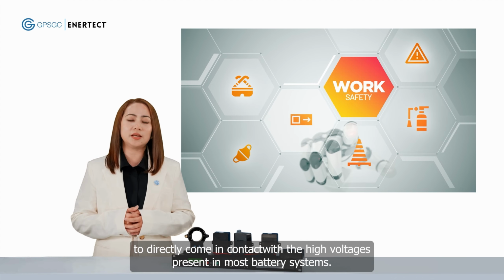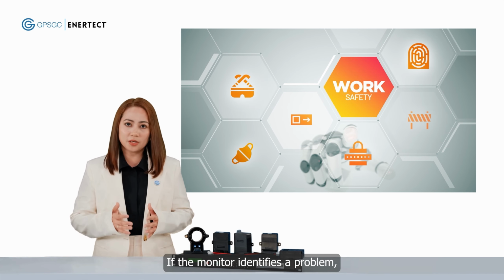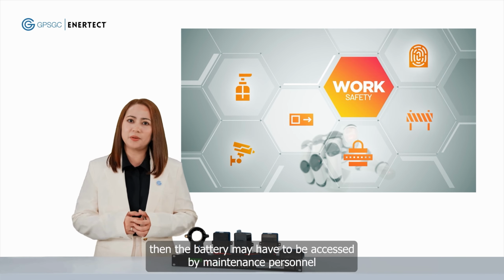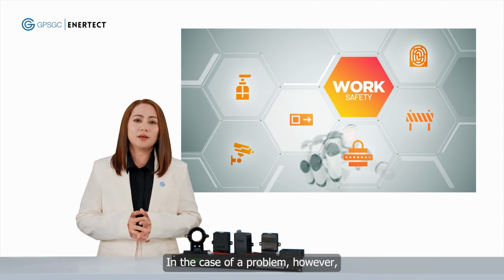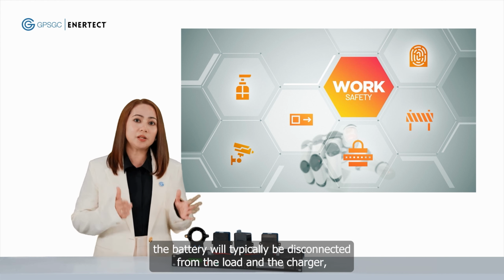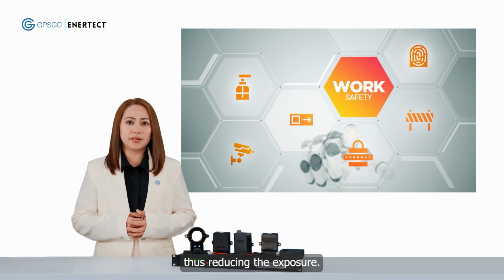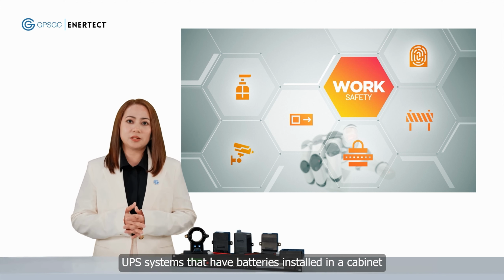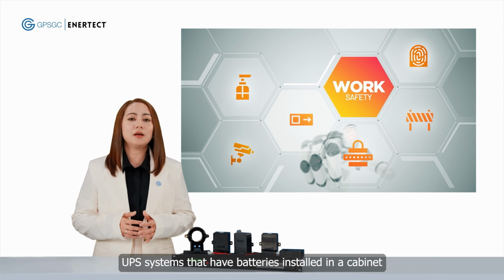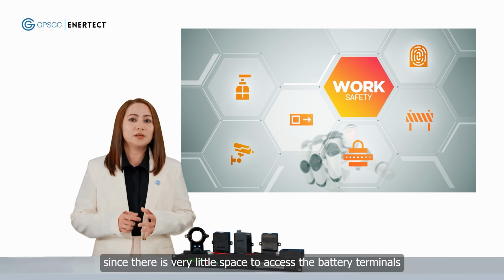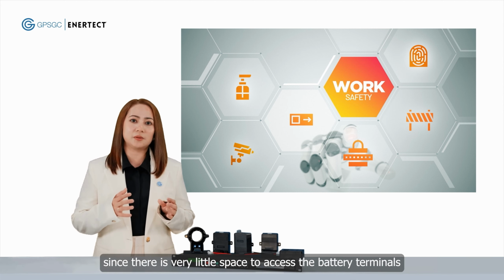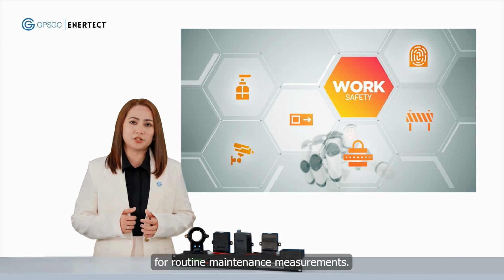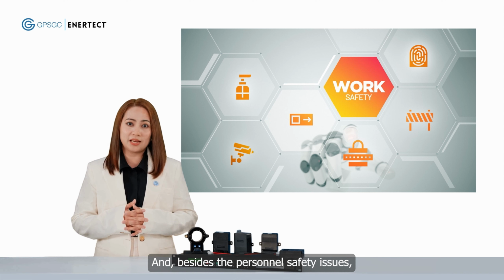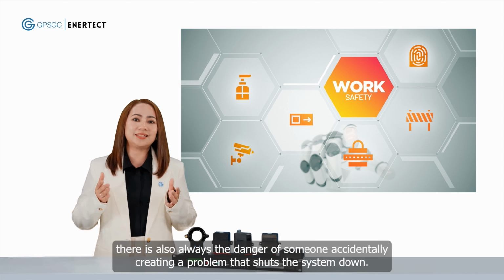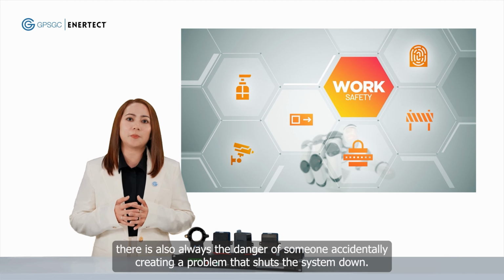Safety. A permanently connected battery monitor reduces the need for maintenance personnel to come directly in contact with the high voltages present in most battery systems. If the monitor identifies a problem, then the battery may have to be accessed by maintenance personnel. In the case of a problem, however, the battery will typically be disconnected from the load and the charger, thus reducing the exposure. UPS systems that have batteries installed in a cabinet are especially hazardous to work with, since there is very little space to access the battery terminals for routine maintenance measurements. And besides the personal safety issues, there is also always the danger of someone accidentally creating a problem that shuts the system down.